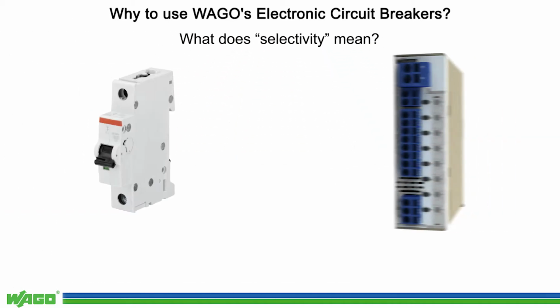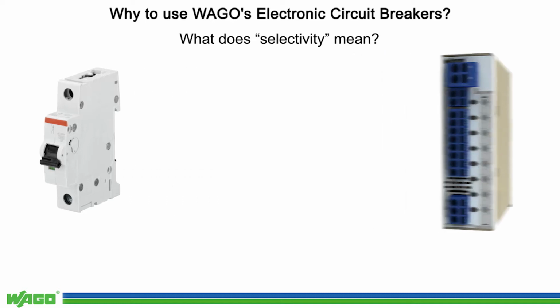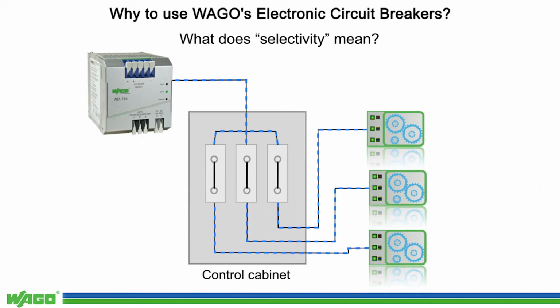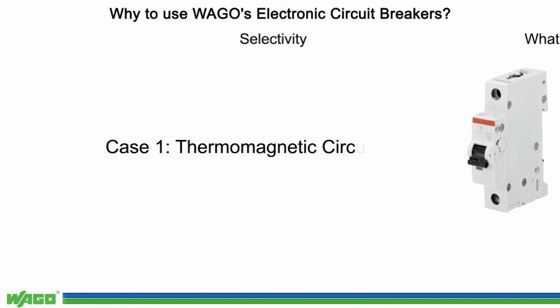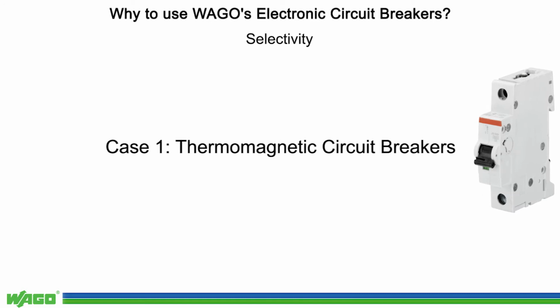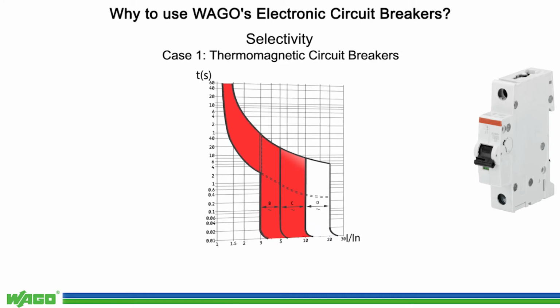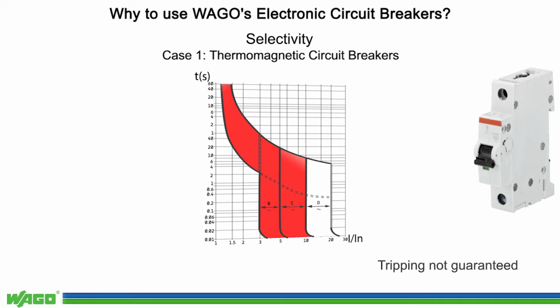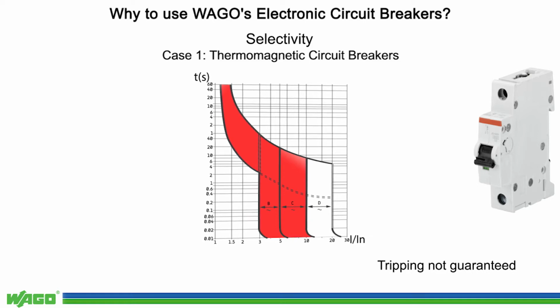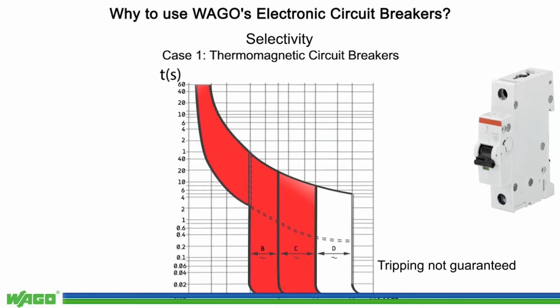Let's talk about selectivity. Selectivity allows an overloaded circuit to be shut down without affecting the other parts of the system. Now let's look at the thermomagnetic circuit breakers more closely. Looking at the trip curve with the characteristics B, C, or D, we might think that selectivity is always guaranteed. In reality, this is not the case, especially under low overcurrent conditions.